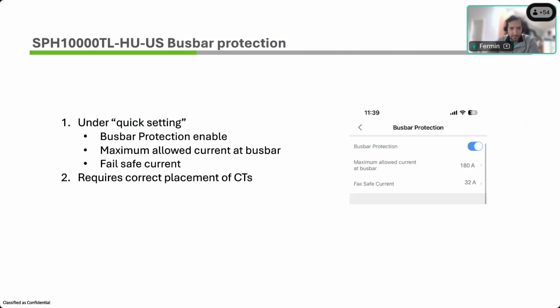It's also equipped with the busbar protection function. This function allows you to control the power that you push to a main service panel, to the busbar that you're interconnecting the inverter to. So in some cases, this allows you to bypass the 120% rule, basically.